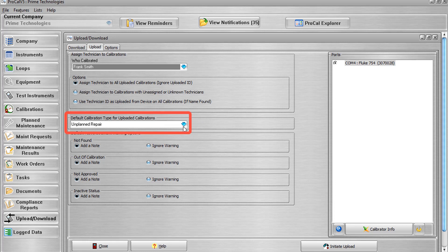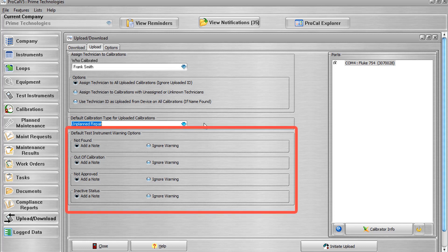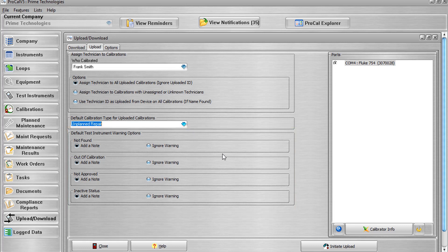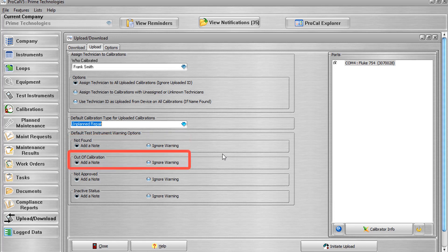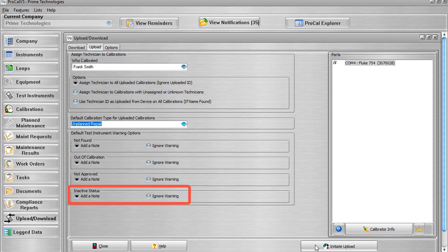The Default Calibration Type for Uploaded Calibrations field is used to apply the selected calibration type to all uploaded calibrations. The Default Test Instrument Warning Options section displays options for how ProCal V5 will handle test instrument warnings during the upload. The calibrator and other auxiliary test standards may or may not be recognized by the system, and certain warnings may apply according to your ProCal V5 company options. These options are: Not Found — if the test instrument is not found in the database; Out of Calibration — if the next calibration date is before today's date; Not Approved — if the test instrument is found but not currently approved; and Inactive Status — if the test instrument has an inactive status.